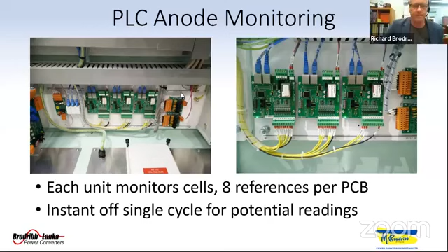Thanks, Ari. So I'm going to talk through the control and monitoring system that we implemented. Rick's already touched on the control and monitoring requirements, so I won't go into too much detail on this one, but I will pick up that the client remote monitoring requirements were particular to have a single Modbus device interface, and they wanted it to be read-only, with a preference to isolate the remote network access from the local network that controlled the devices.